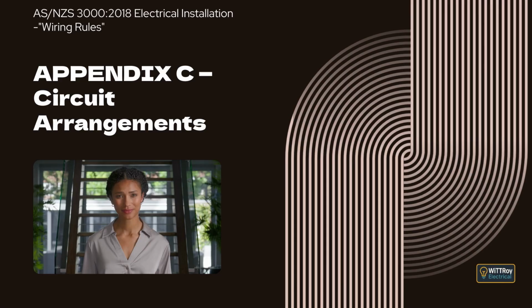Clause C2.1, After Diversity Maximum Demand. This clause explains that circuit current must not exceed the rating of the protective device, and the protective device must not exceed the current carrying capacity of the conductors. For a single item of equipment, the circuit current is simply the load current of that equipment. When more than one item is connected, adding all loads together would be safe but overly conservative. In real installations, equipment usually does not operate all at once or at full load for long periods. Under these conditions, the expected current is estimated using diversity, and this estimated value is called the after diversity maximum demand.